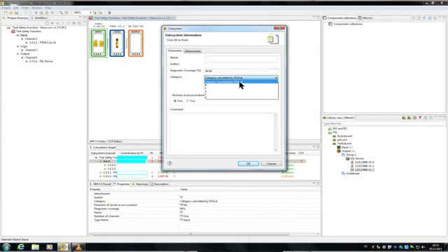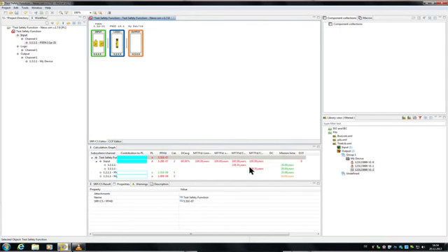And I even can change the category, either to do it automatically through this system, so it does a calculation, or I can say, okay, no, this is only category 1 or category 2, and it changes accordingly. So right here I changed it to category 2, DC 60%, from initially a category 4 to 99%.